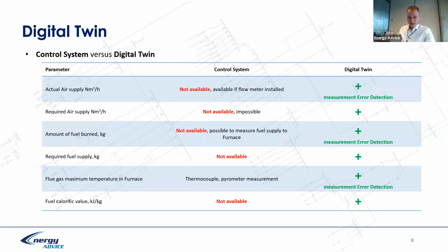I put a couple of tables to compare the capabilities. For example, we have the control system and we have the digital twin solution. The parameter: actual air supply. In fact, in the control system it is not available unless we put in an extra metering device. However, a digital twin allows us to calculate the amount of air supplied to a furnace, if you're talking about the boiler. So in fact, indirectly we can calculate the air supplied.